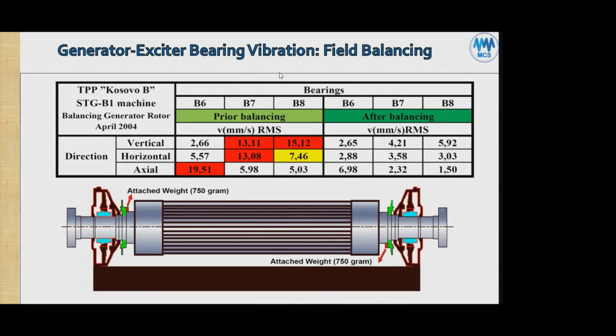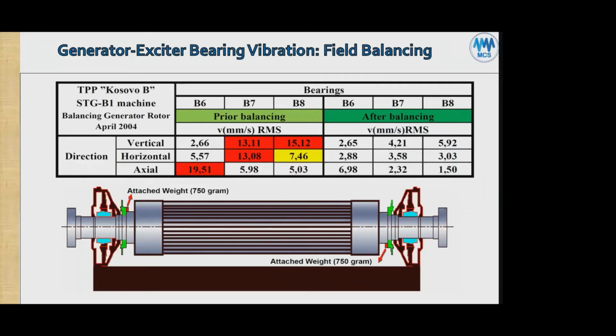So I believe they were using the older technology of shaft reading seismic probes. I doubt it is the bearing housing vibration. It looks like a direct shaft reading, where they put a seismic accelerometer on a shaft rider, they call it, and that measures the shaft vibration directly. That was the old method of measuring large steam turbine generation units' vibration. We still have it for some old steam turbines in Australia, and yes, they call them shaft riders. That's correct. Okay. In Australia, you have it now.